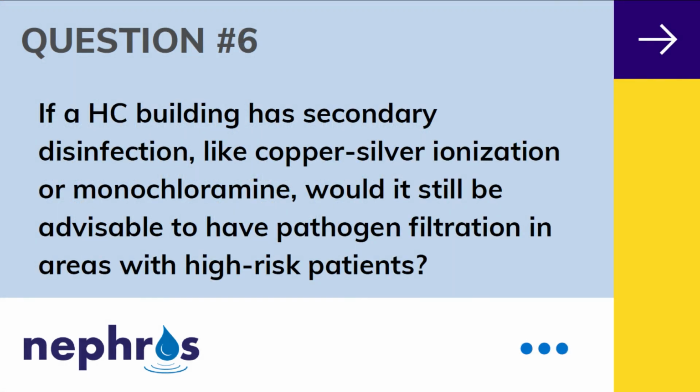If a healthcare building has secondary disinfection, like copper-silver ionization or monochloramine, would it still be advisable to have pathogen filtration in areas with high-risk patients? If water sits idle for almost any length of time, with the doubling time of a gram-negative water bacteria being 20 minutes, you can imagine how high the numbers could get. The problem we run into is the chlorine goes away with time.